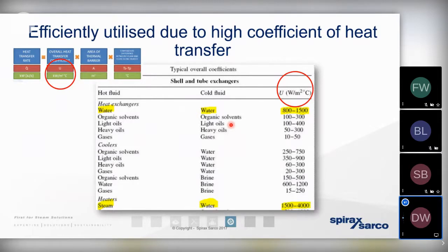So the benefits of a smaller heat exchanger are that we only require a smaller footprint of space in the plant room. And if we're holding less water in the body of the heat exchanger on the secondary side, we get fewer standing losses. We get less heat radiating out into the plant room.